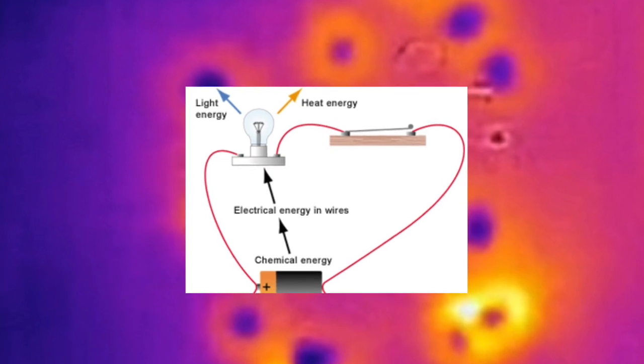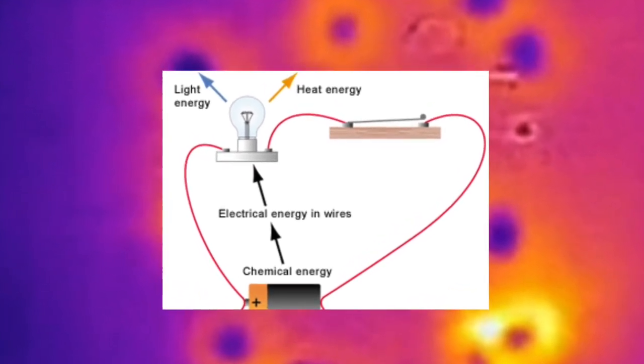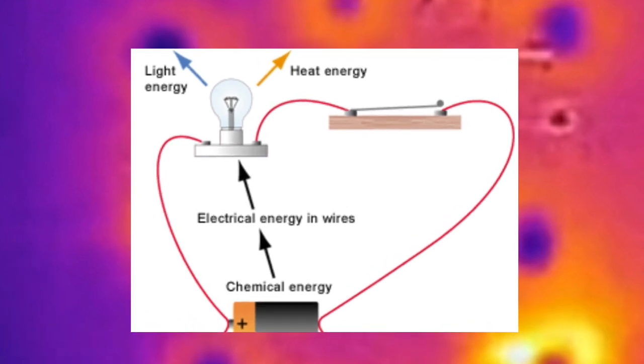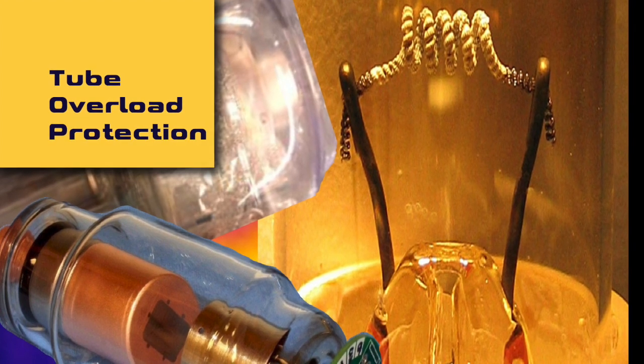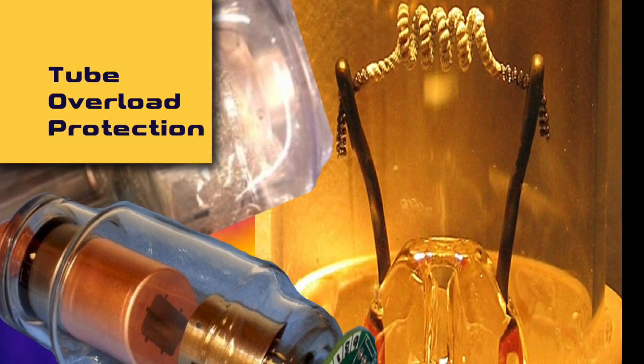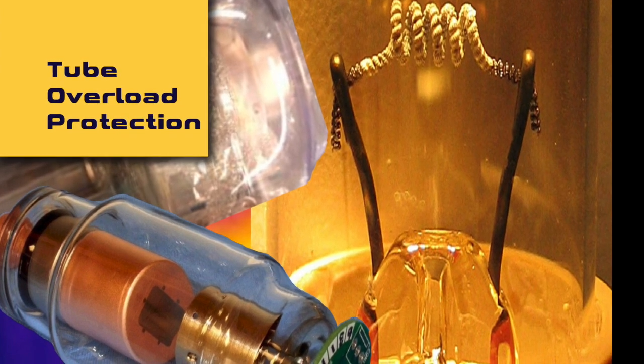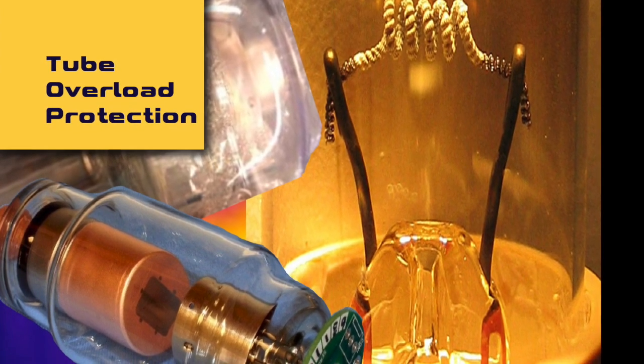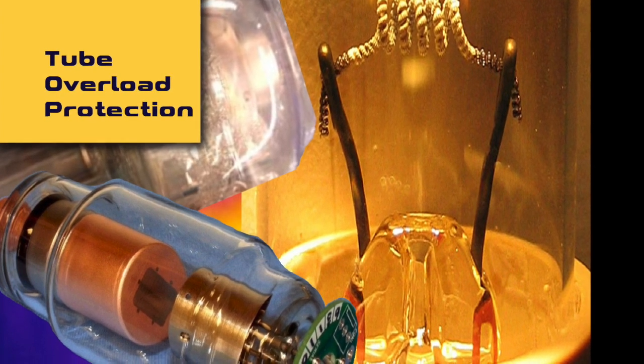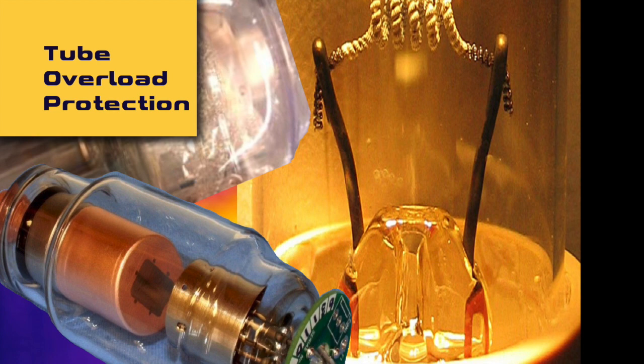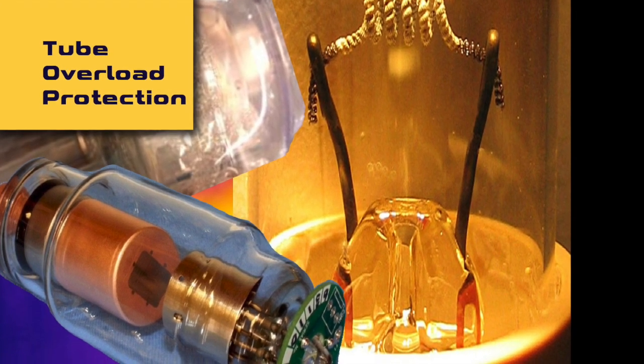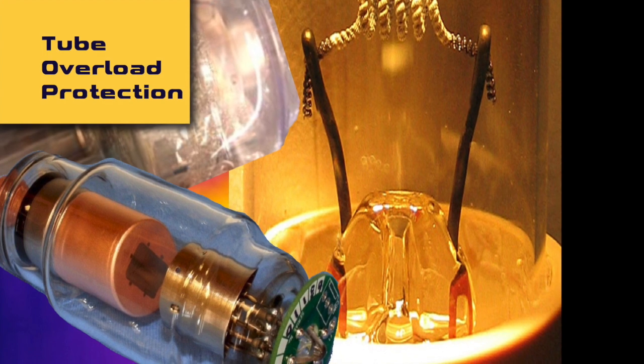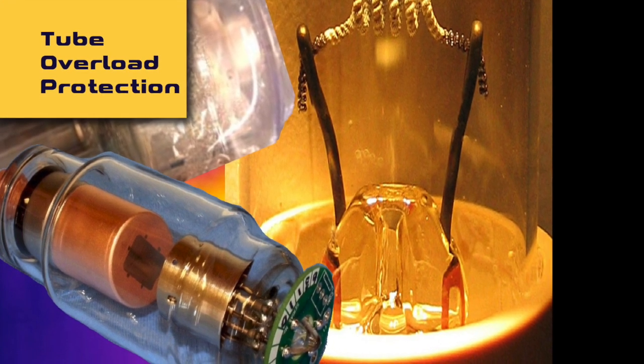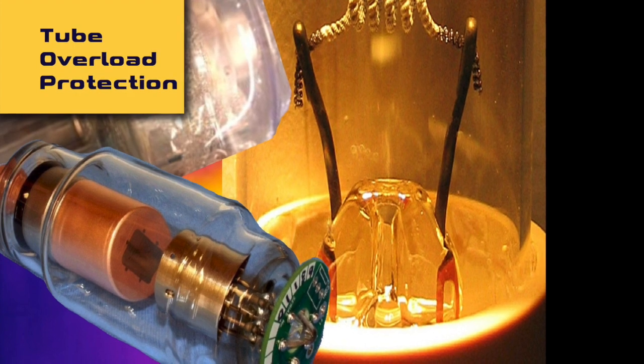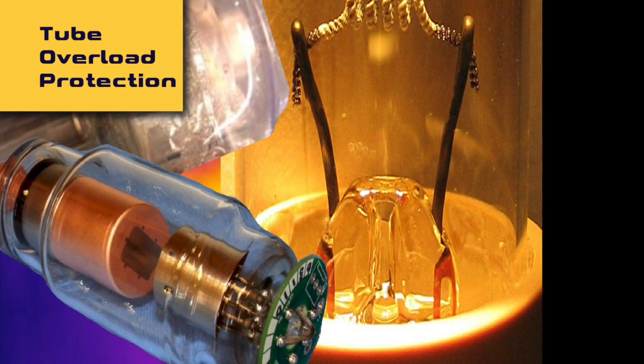Only 1% of the energy used in the production of X-rays contributes to the useful beam. The rest is converted to thermal energy or heat, and this can damage the tube. For this reason, measures are taken to avoid overloading the tube. These protective measures and fail-safes should be tested regularly to prevent X-ray tube damage. One preventative measure that may be taken is proper warming up of the anode, as applying excessive heat to a cold anode too quickly may cause it to crack. Most equipment will employ an overload protection circuit to prevent things of this nature from happening. Testing should be performed after calibration of technical factors and should be repeated annually or more frequently if there is evidence or question of a malfunction of this feature.